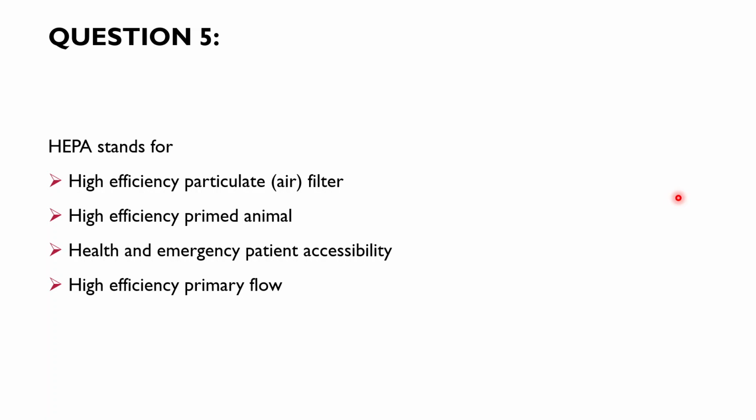HEPA filters are placed inside our biosafety cabinets, in the exhaust system, so that they effectively trap all known infectious agents and ensure that only microbe free air is discharged out of the hood. So what do you think the right answer is?